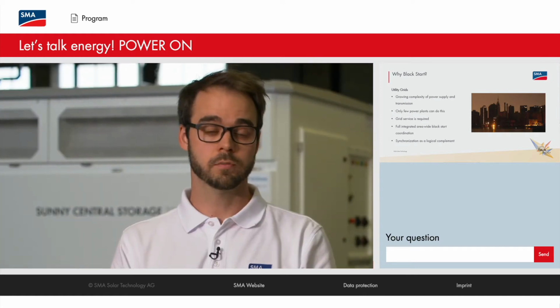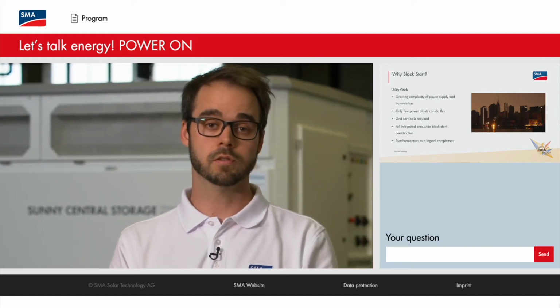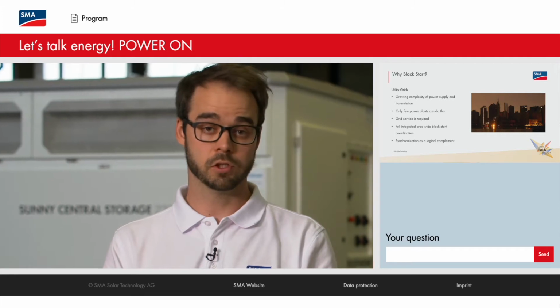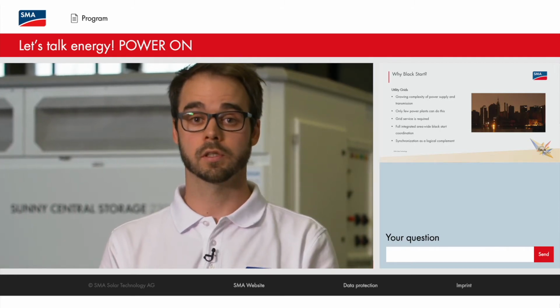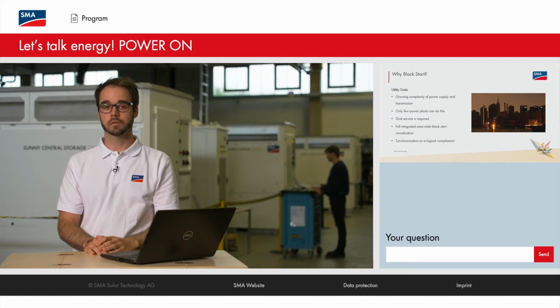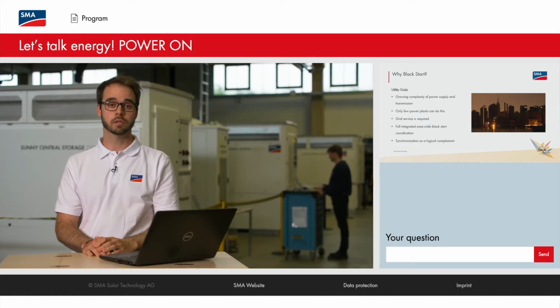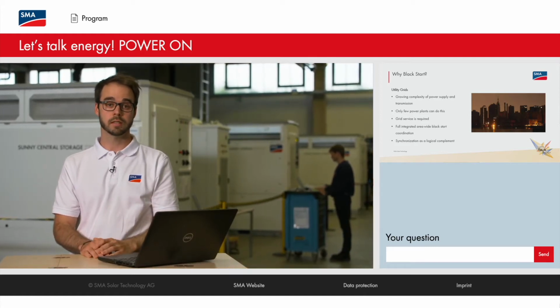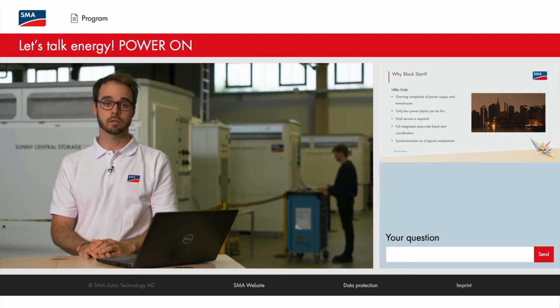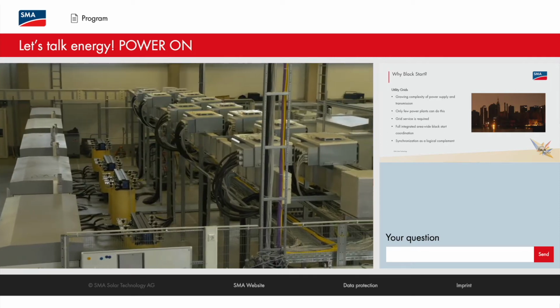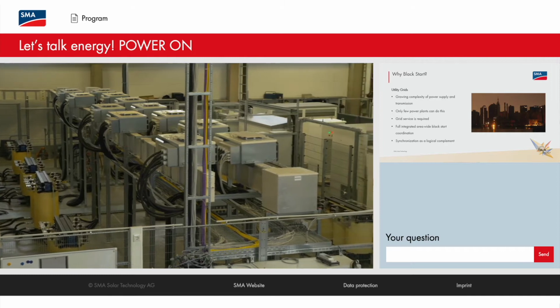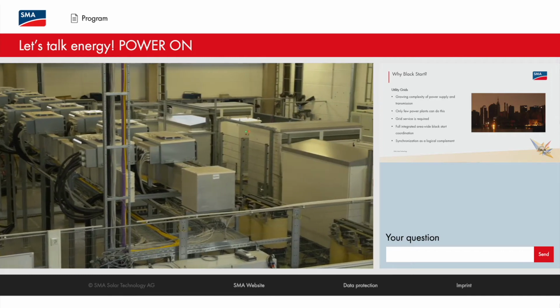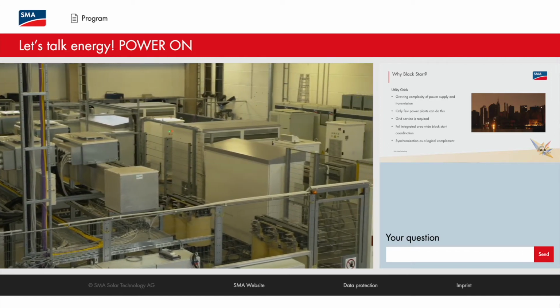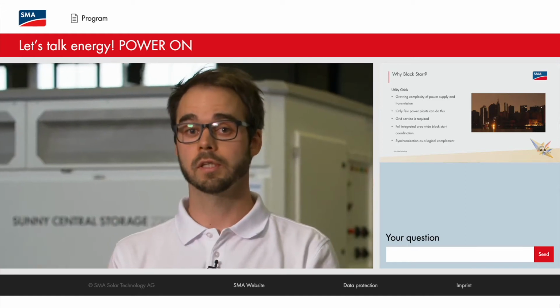So the special system functionalities of such a hybrid system would be black start functionality and synchronization functionality. Imagine if there's a power outage of the overlaid grid, it would be possible to completely isolate the small town from the overlaid grid and power it up with black start functionality, run it for a couple of hours depending on battery size and renewable integration, and synchronize it back to the overlaid grid.